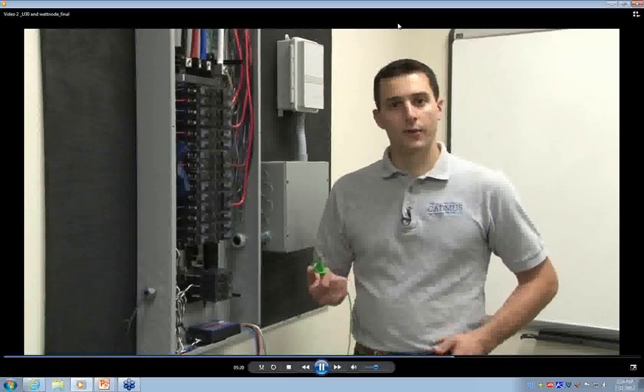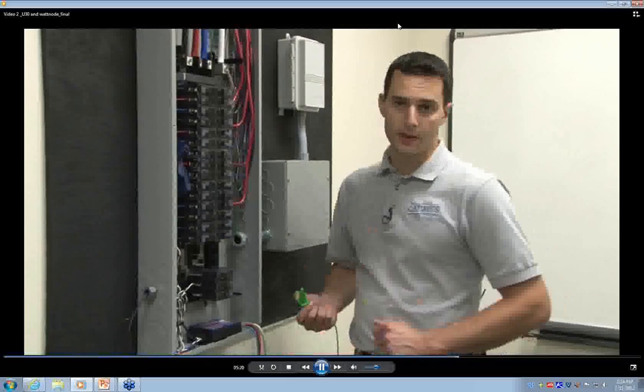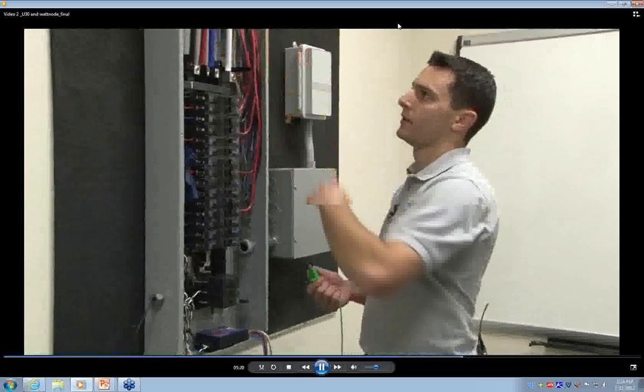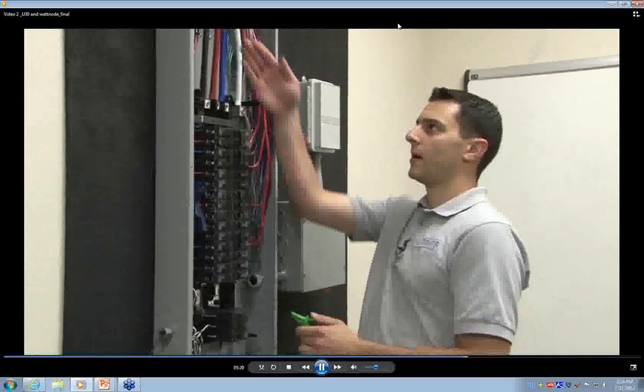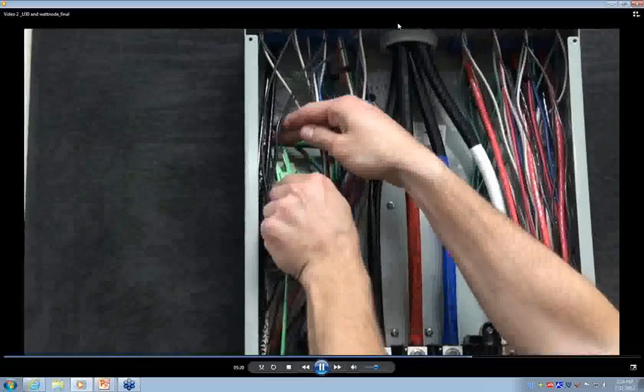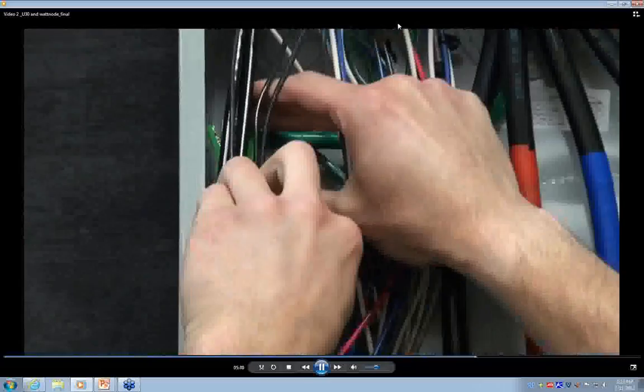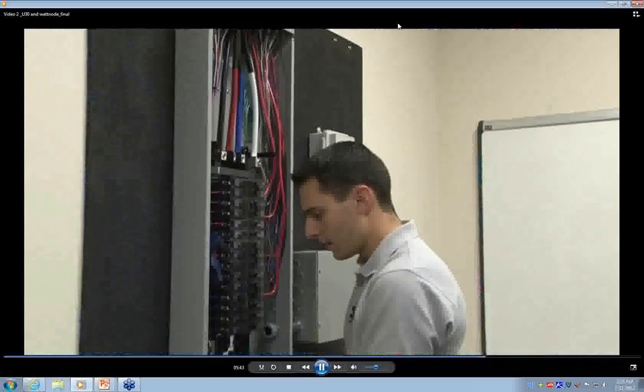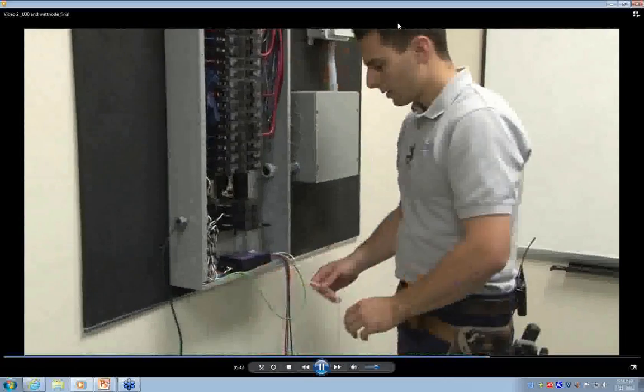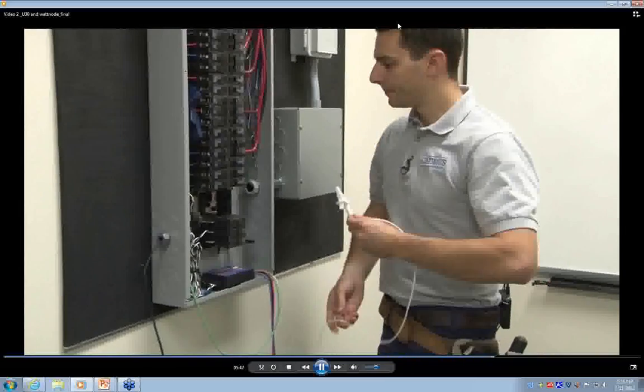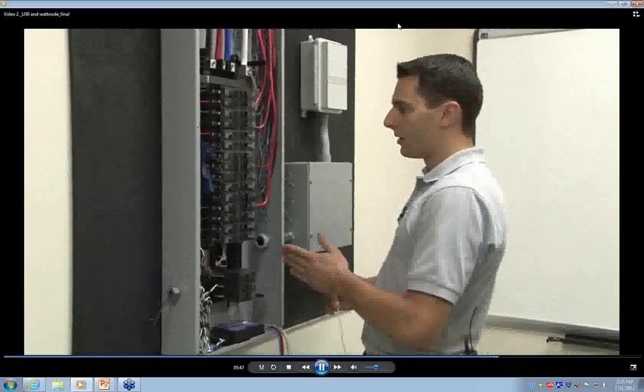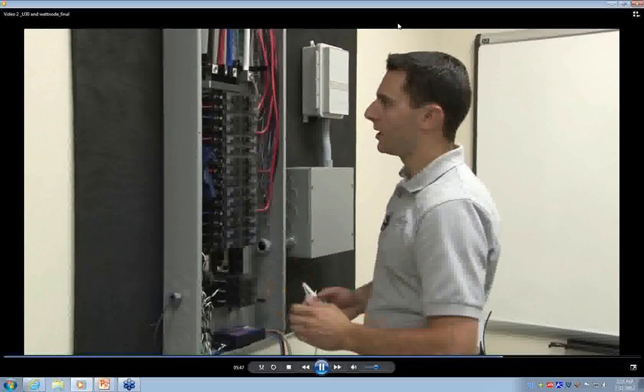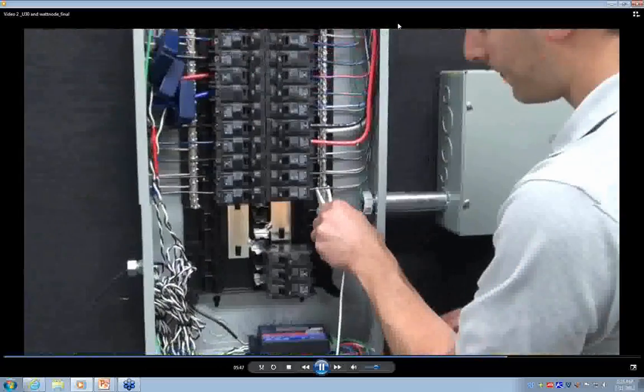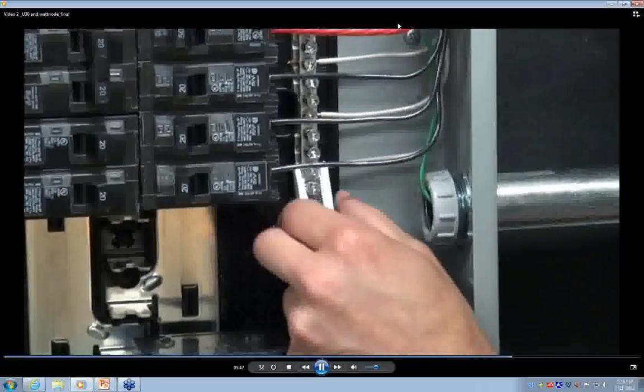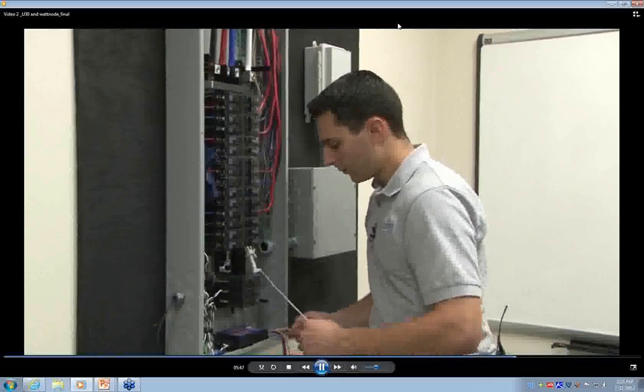We'll start with the green ground voltage lead. This can be connected to any part of the metal in the enclosure or one of the two ground bus bars in this panel. For this, we'll connect it up in this corner. We'll want to make sure it's nice and secure, and we'll run the cable safely along out of the way of the other cables. The next connection will be the white neutral voltage lead. In this particular panel, the neutral bus bar is on this side and this side, and for convenience we'll go right over here. Again, we'll make sure we have a good secure connection, and we'll neaten up our lead.